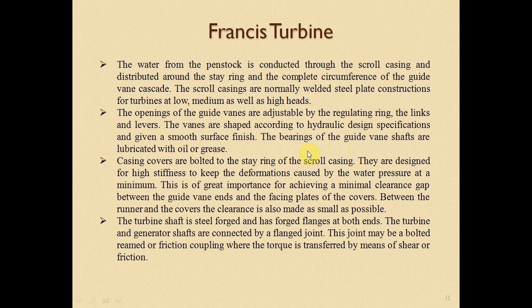The bearings of the guide vane shaft are lubricated with oil or grease. Casing covers are bolted to the stay ring of the scroll casing. They are designed for high stiffness to keep the deformation caused by water pressure at a minimum. This is of great importance for achieving a minimal clearance gap between the guide vanes and the facing plates of the covers. Between the runner and the cover, the clearance is also made as small as possible.